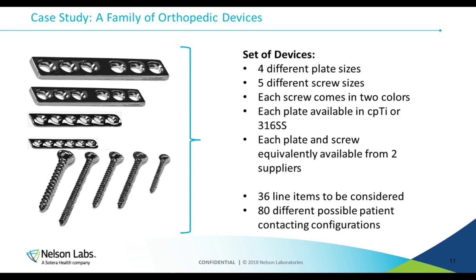And if you think about how this could be used in a clinical situation, there are lots and lots of different combinations of the way this could be organized that contact a patient. It could be the smallest plate with 4 or 5 of the same screw or different screws and so on. So you could approach this lots of different ways depending on how you would family group things. Certainly the worst case, or the most expensive case, would be to try to test all 80 different possible patient contacting configurations, or to somehow test all of the different components independently. But usually that's not required, and we'll step through this and I'll explain why.